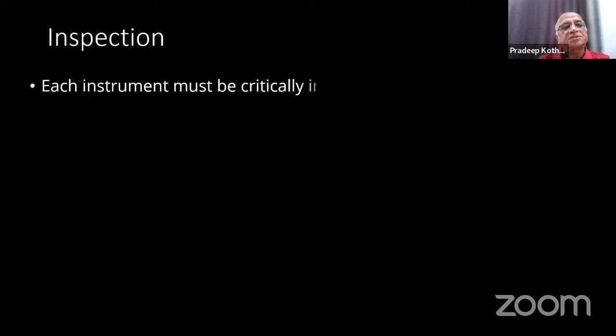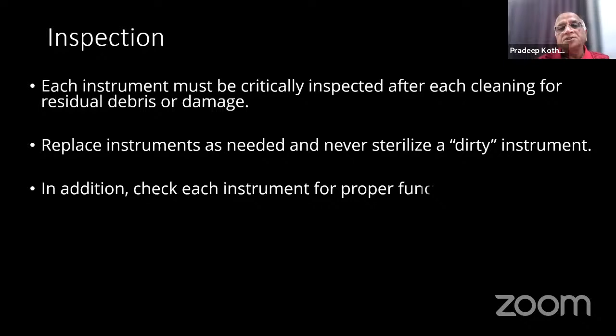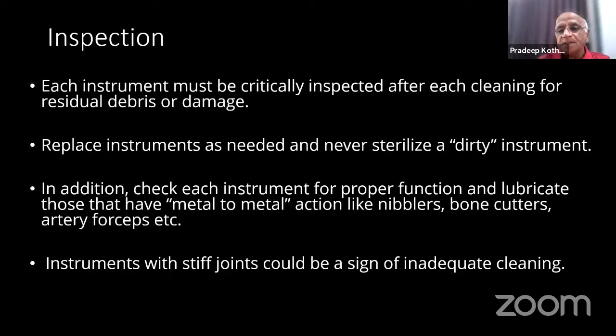Every instrument must be critically inspected after cleaning for residual debris or damage. Replace the instruments as needed. Never sterilize a dirty instrument. In addition, check instruments for proper function and lubricate those with metal-on-metal action, like nibblers, bone cutters and artery forceps. Instruments with stiff joints could be a sign of inadequate cleaning, or they are repeatedly used. So go through each instrument. Next step comes packing.